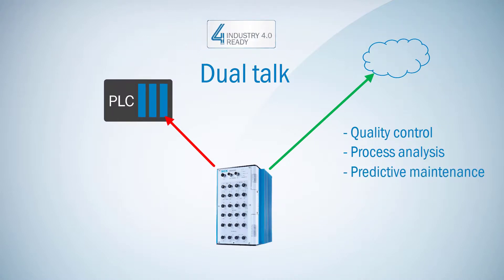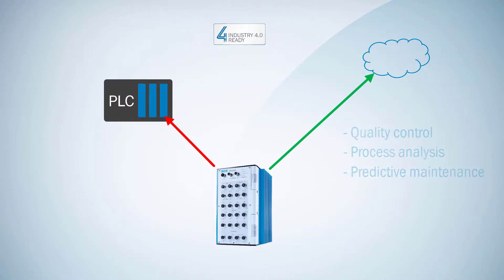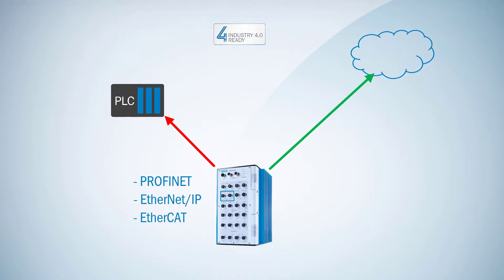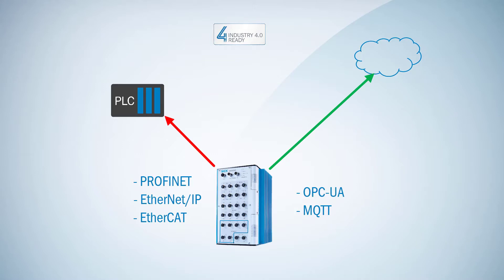For communication to the PLC, the SIM 4000 offers fieldbus protocols: PROFINET, Ethernet/IP, or EtherCAT. Communication to cloud services is available via the Ethernet ports using innovative M2M protocols like OPC UA or MQTT.